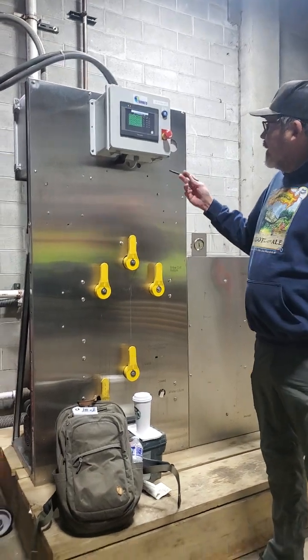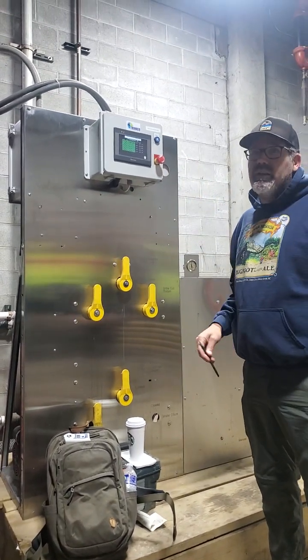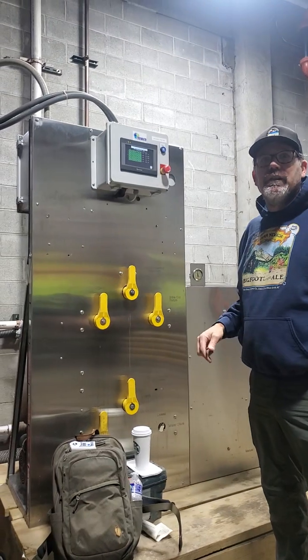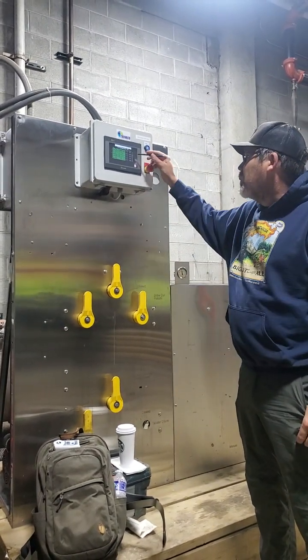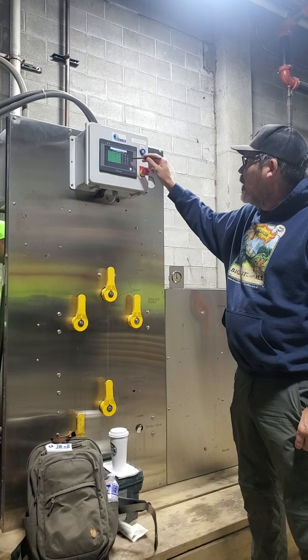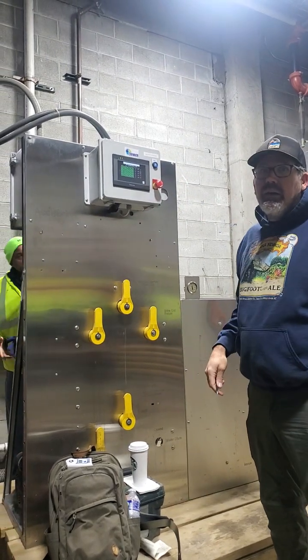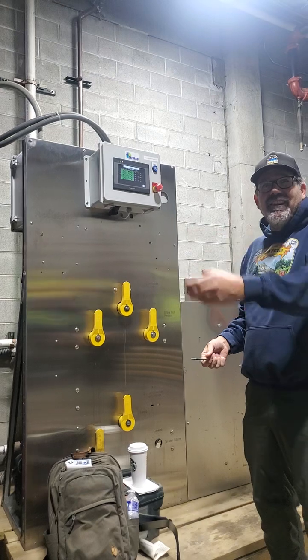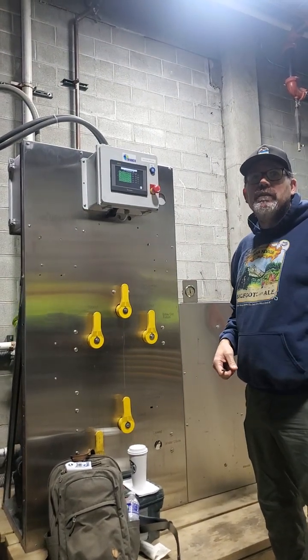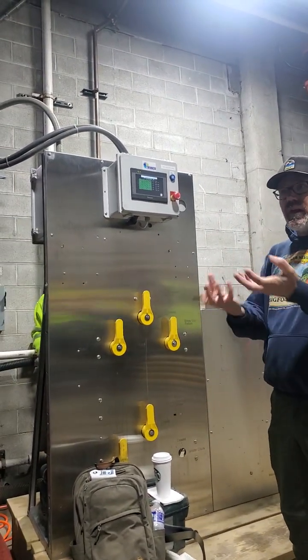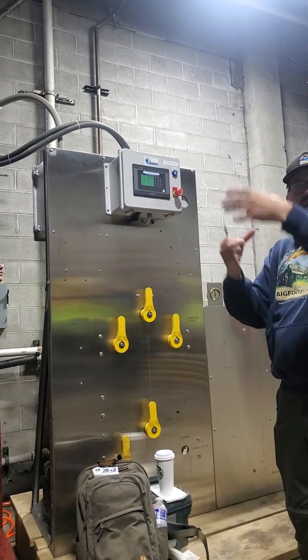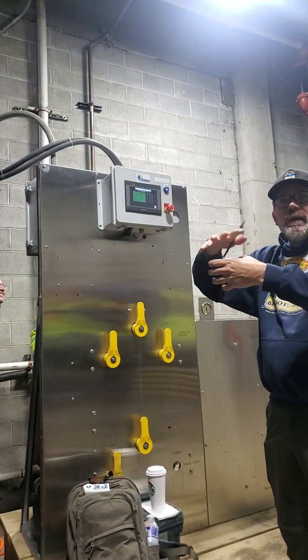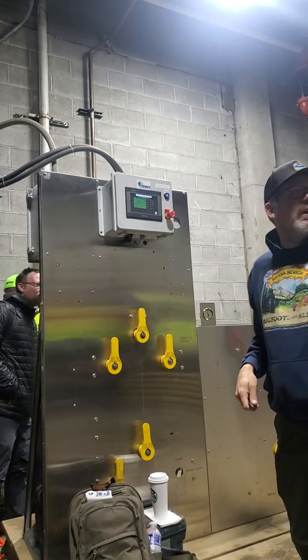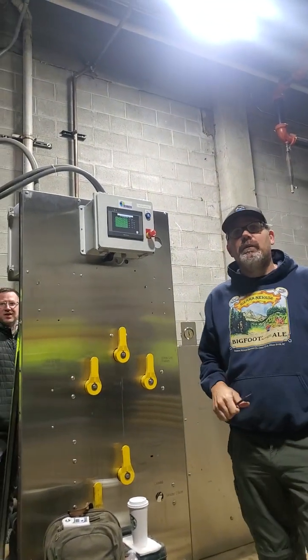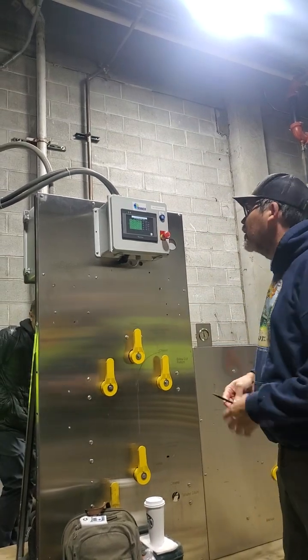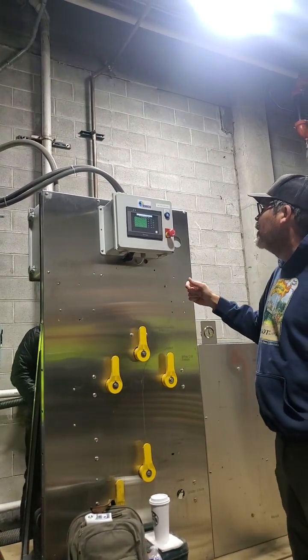I think that covers it. That's really the main thing you'll have to troubleshoot, this pressure transducer stuff, and most of it's inside. For the brine one out there, I know it's a lo-fi fix, but take a water bottle, cut it off, and slip it over the top. It keeps air circulating to dry it out, but keeps snow and rain from sitting directly on top of it. Especially if these are sitting outside, just put a water bottle over the top. It protects it pretty well usually.